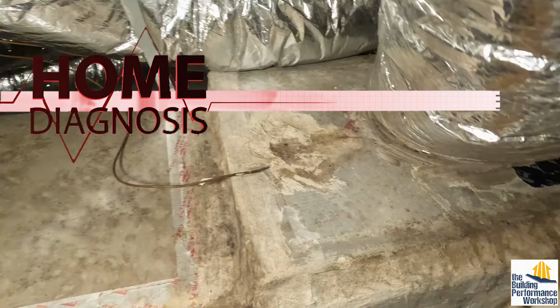This is where dew point temperature comes in. I don't keep my thermostat below 72 degrees in the Springfield, Massachusetts area, because if you look at the outdoor dew point on a peak humidity day, it's right around that point. So now you've created a situation where anywhere indoor air and outdoor air meet, you're going to get condensation. Do you think that happens in places you can see and know about, or in hidden places you don't know about that build up over time? Stay tuned for Home Diagnosis Season 3 for pictures of that.